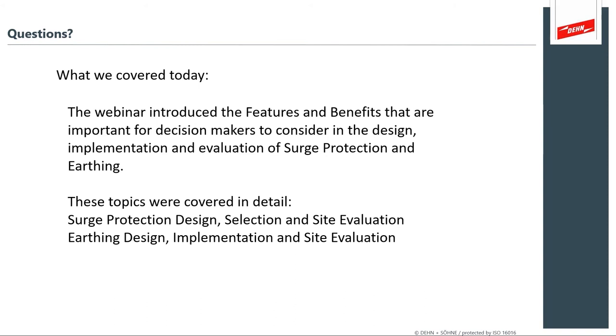I would just like to add that you select a certain lightning protection level in your risk assessment, and that guides you to what SPD you need to select. And you'll notice when you do the risk assessment that if you select a more stringent lightning protection level, say at lightning protection level 3, 2, or 1, that's higher than a lightning protection level 4, the risk keeps on reducing even though you've just implemented the same surge protection measure.